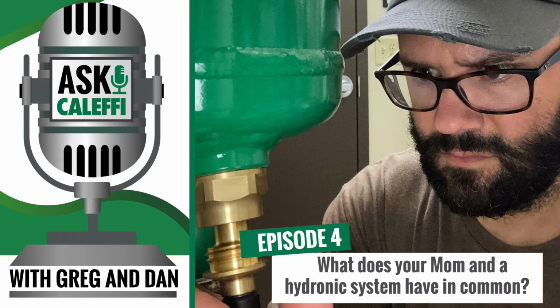Right. And we have to remember, every time we're talking a separator of any kind, it is a multi-pass device. Right. Is that similar to a Y strainer, Greg? Not at all. We definitely know that Y strainers are more restrictive, and those are typically a one-pass filter type device. Right. And those you will tend to get more of a pressure drop through as they start to collect dirt and debris because they don't have that large body. Right. They'll plug up where a separator, unless the system is really dirty, should not plug up. No, not if you're doing your maintenance properly.